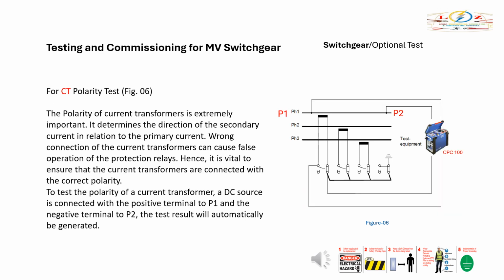For CT polarity test, as shown in the arrangement drawing in Figure 6. The polarity of current transformers is extremely important. It determines the direction of the secondary current in relation to the primary current.